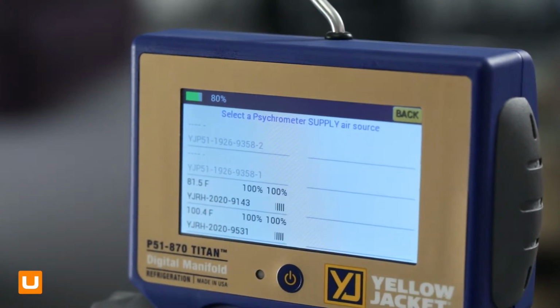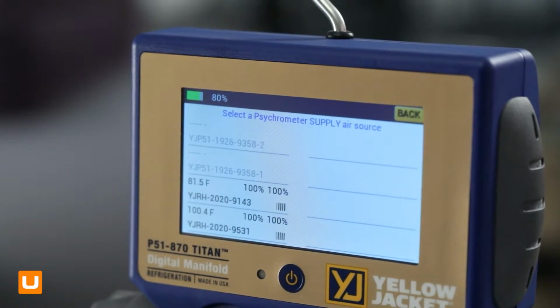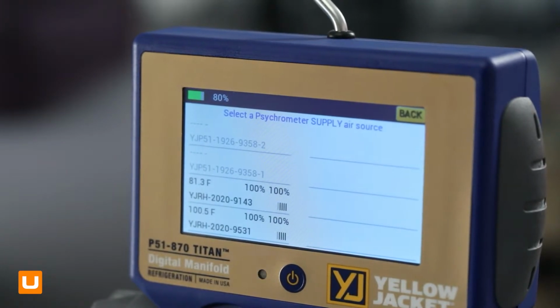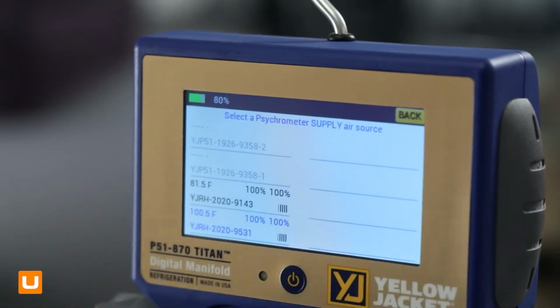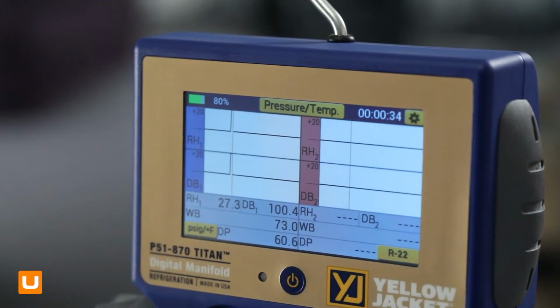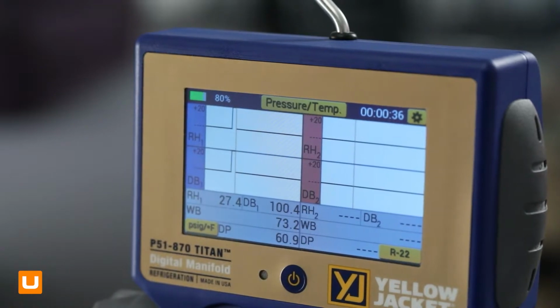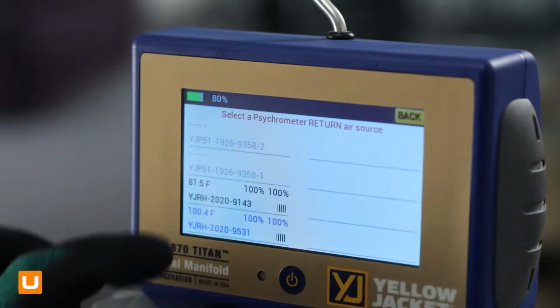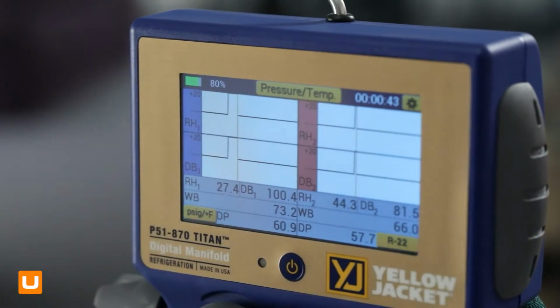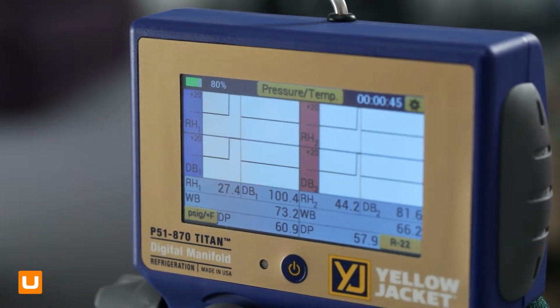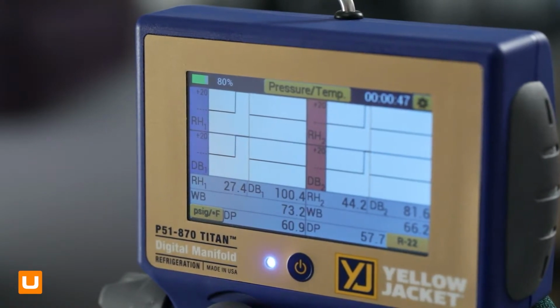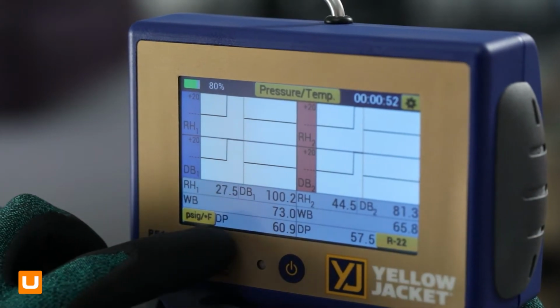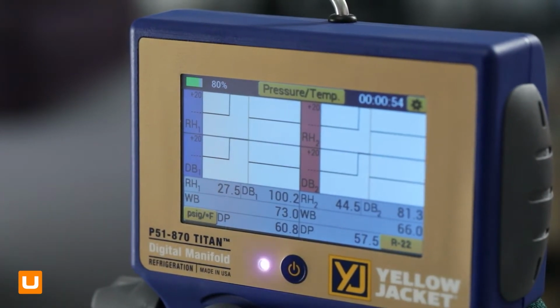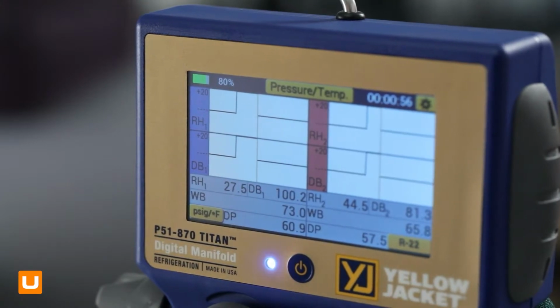A list of available YJACK psychrometer devices will appear. To assign the supply air readings, tap on the Bluetooth ID of the psychrometer placed inside the supply air duct. Repeat this process for the return air on the right side of the screen. The supply and return air relative humidity and dry bulb temperatures are graphed, and numeric readings are displayed for the relative humidity, dry bulb, wet bulb temperatures, and the dew point.